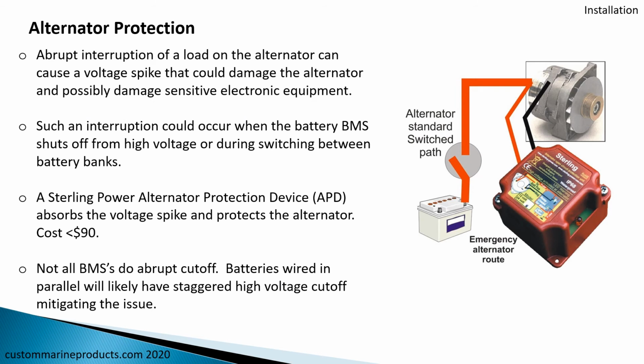An abrupt interruption of the load on an alternator that is putting out a full current could cause a voltage spike that could either damage the alternator or possibly damage sensitive electronic equipment. Now, this could happen when a heavy load is immediately shut off, or for example, when the 1-2-both battery selector switch is defective and different batteries are selected, or when a BMS shuts off when the full battery voltage is achieved.